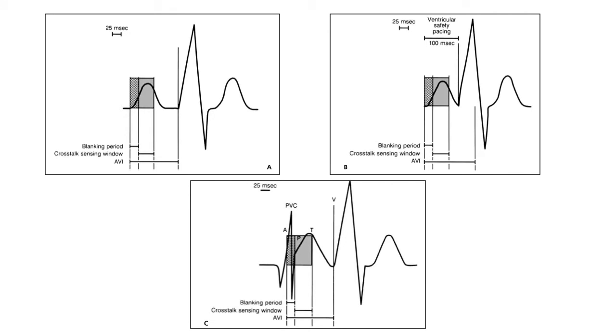When we look at the AV interval, we should consider it as a single interval with two parts. The whole AV interval corresponds to a programmed value, starting from the paced or sensed atrial beat till the next paced ventricular beat. And on atrial output, a timing period on the ventricular channel known as the ventricular blanking period will start. This period would coincide with the earliest part of the AV interval, and it is meant to avoid the sensing of an event or a stimulus of one channel in the opposite channel.